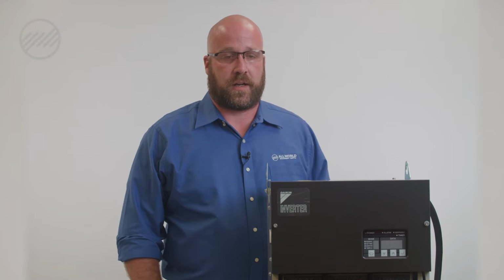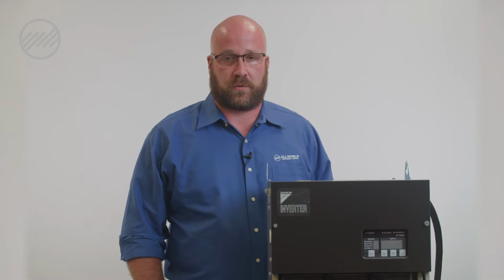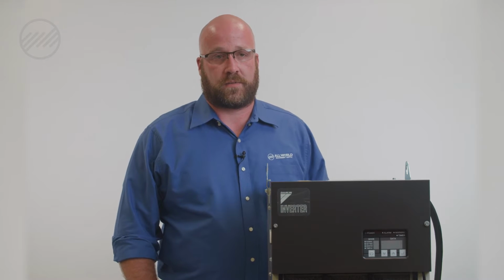Daikin oil chiller units provide a variety of different ways to troubleshoot alarms on the unit, as far as for low voltage, oil flow, and also cooling issues.